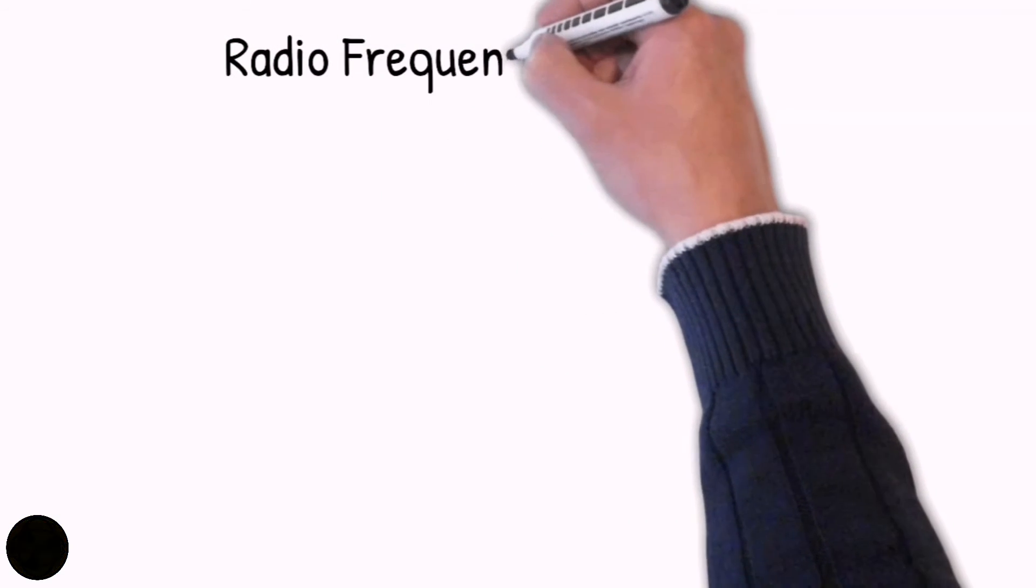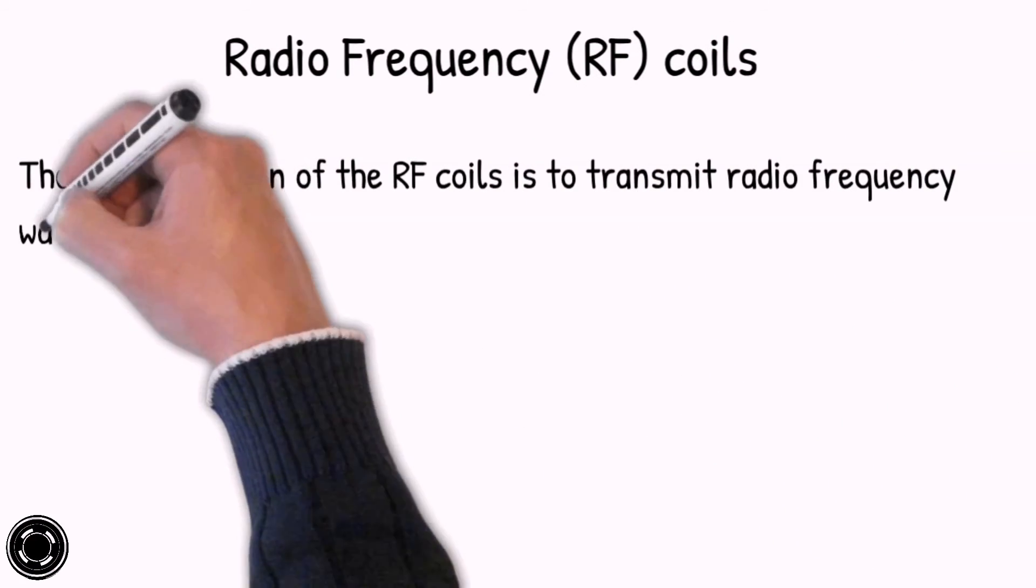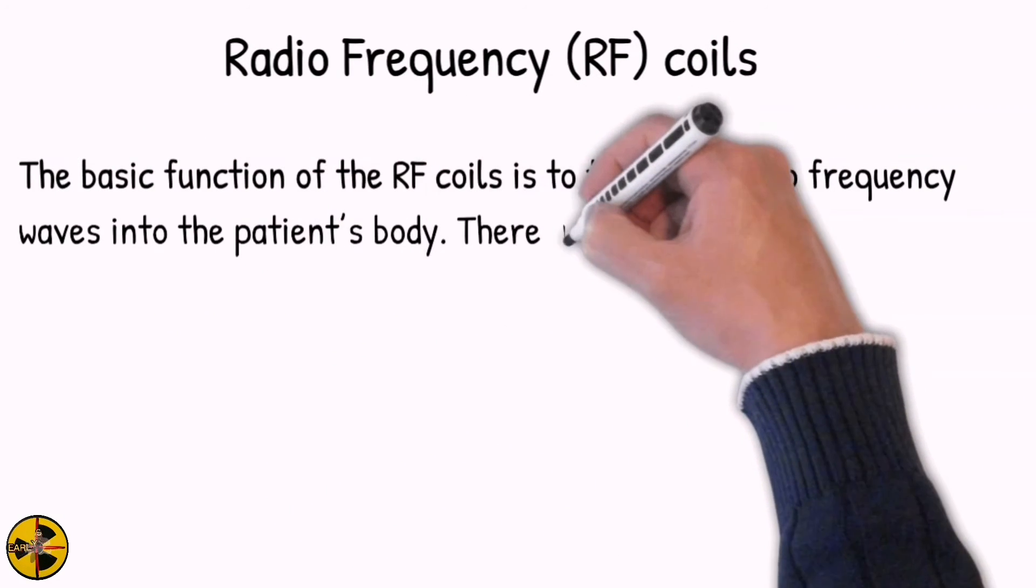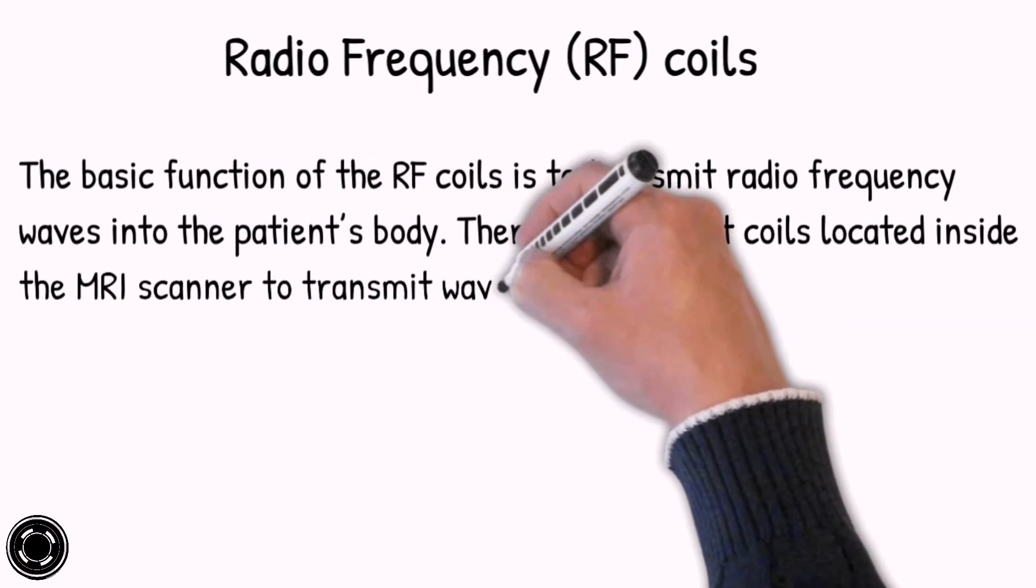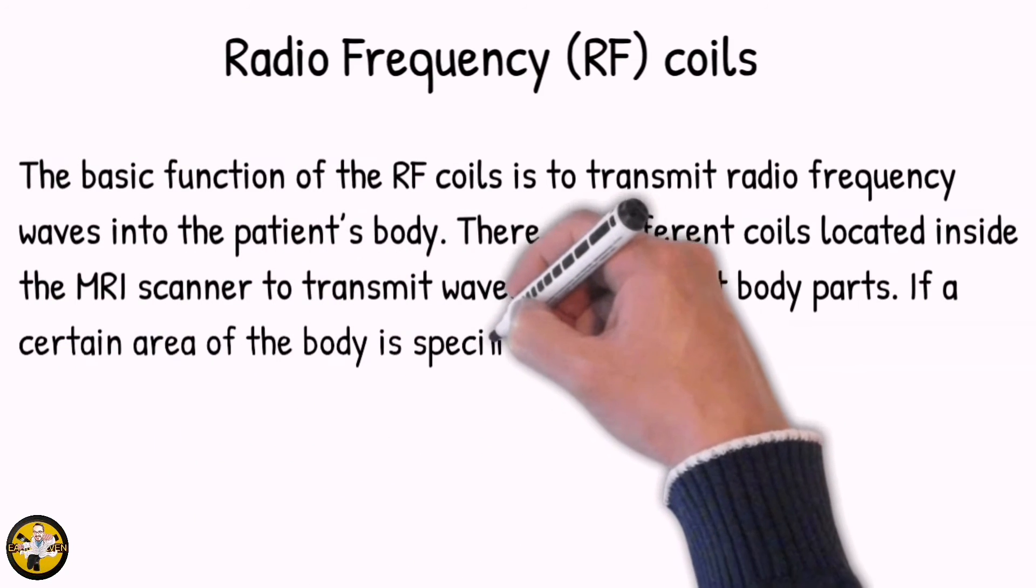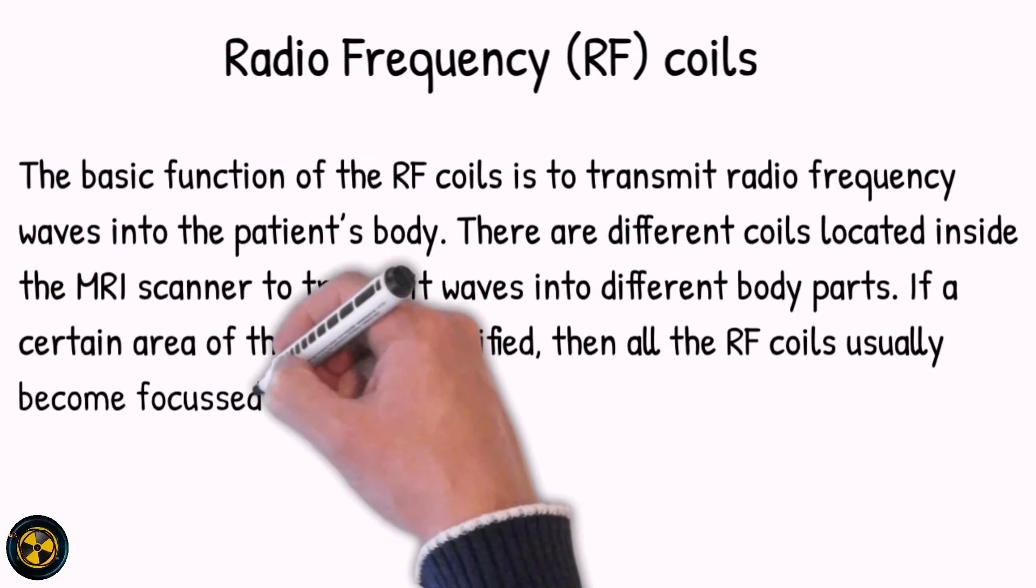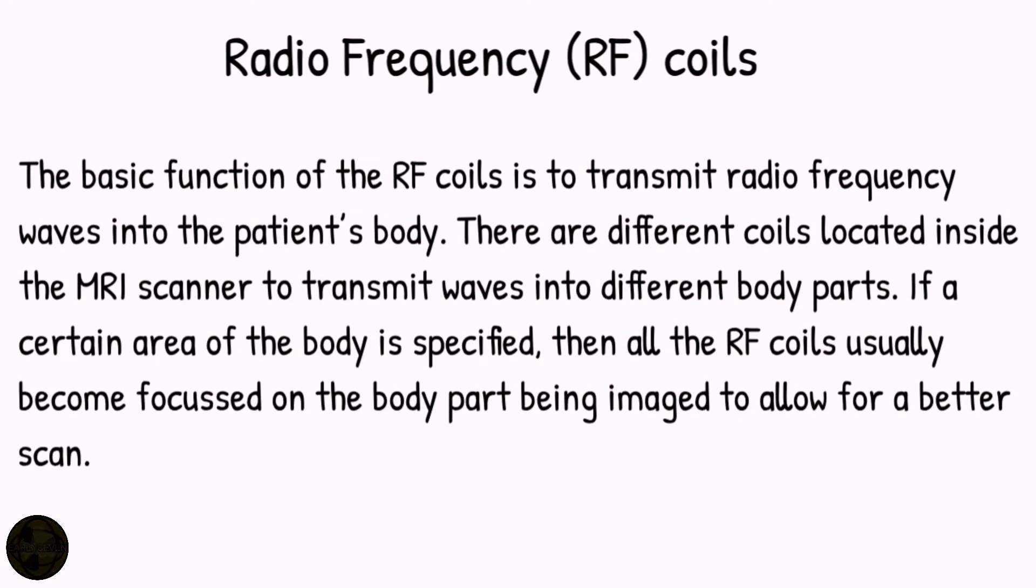The next component is the radio frequency coil, or the RF coils. The basic function of the RF coil is to transmit radio frequency waves into the patient's body. There are different coils located inside the MRI scanner to transmit waves into different body parts. If a certain area of the body is specified, then all the RF coils usually become focused on the body part being imaged to allow for a better scan.